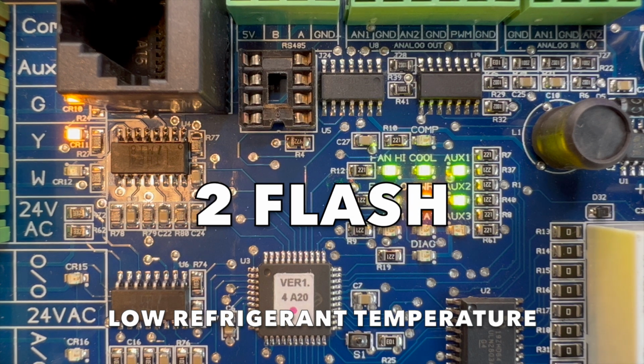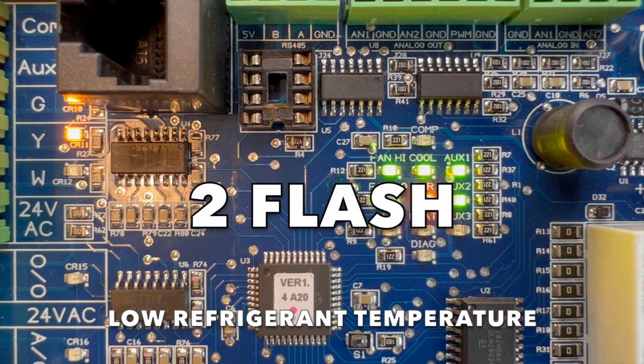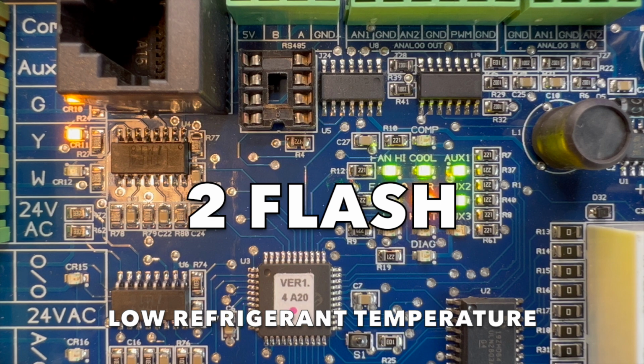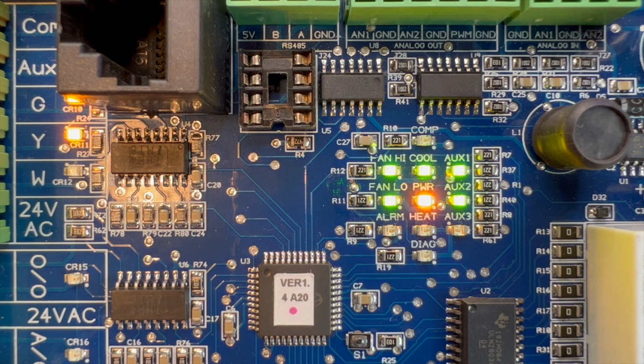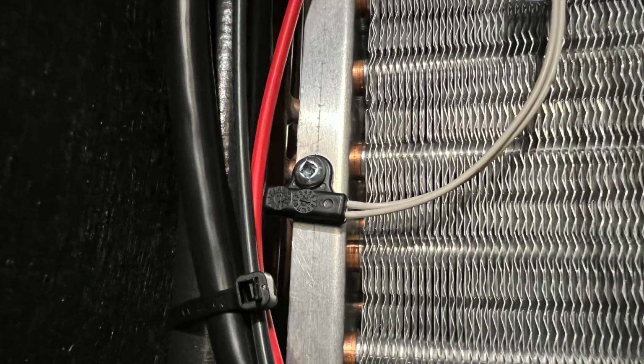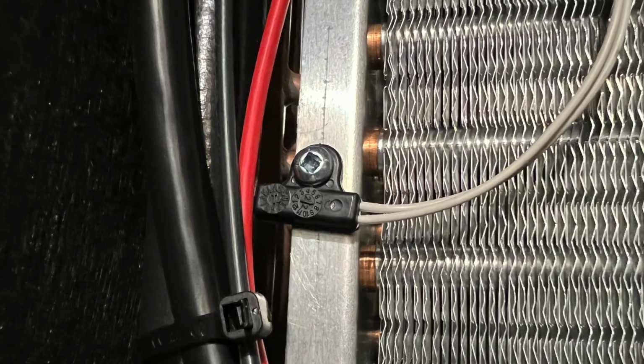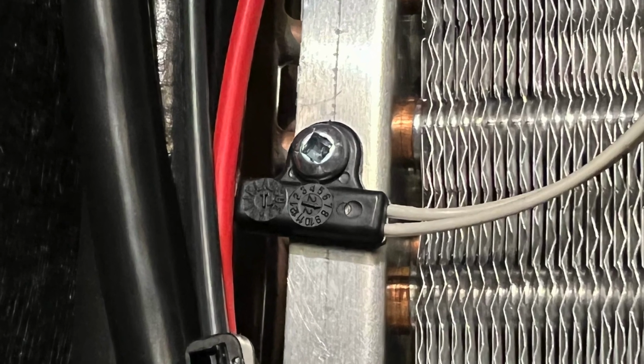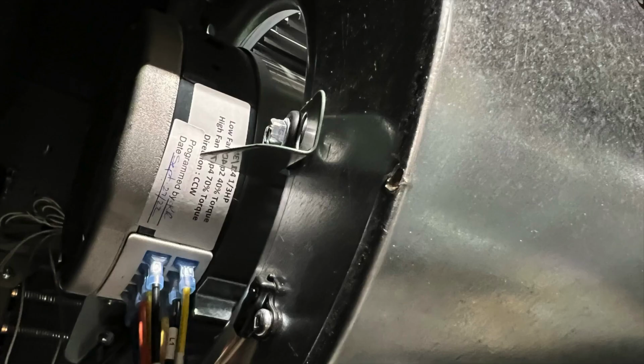2 flash, low refrigerant temperature. This fault occurs when the evaporator coil temperature drops below 40 degrees Fahrenheit and it resets when it goes above 65 degrees Fahrenheit. This sensor is attached to the evaporator coil approximately half the way up. Sometimes it's around the other side where the return bends are. Possible causes are loose sensor wiring, restricted airflow, low fan efficiency, or the ambient air is too cold. Early stages of refrigerant leaks can lead to coil icing, which may cause this fault.